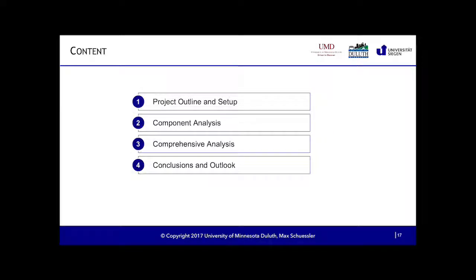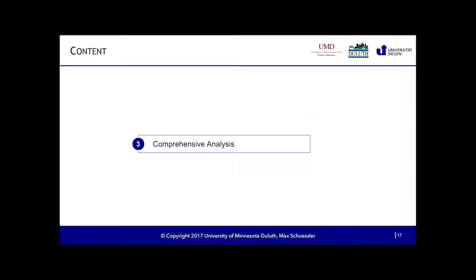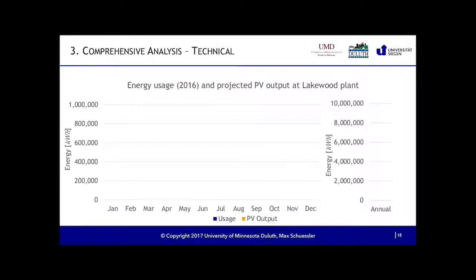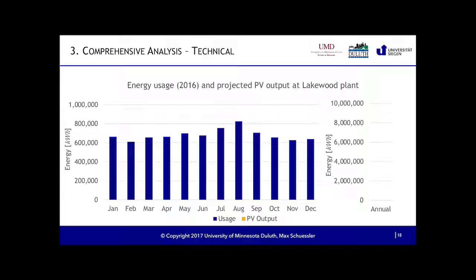Okay, now these were a lot of tiny little things in those components. Now I looked at the bigger picture: what happens if I combine all those elements together? For that, this is what we have as an energy use in the course of 1 year, in 2016, at the Lakewood plant, around about 600,000 kilowatt hours per month that we consume there. And my PV system, remember, is a 1.5 megawatt system, so it's not a really small PV system, but it's only contributing around about a quarter of the whole load we have down there. On an annual basis, that is 8 million kilowatt hours of energy draw and 2 million kilowatt hours that we can produce down there and could offset.